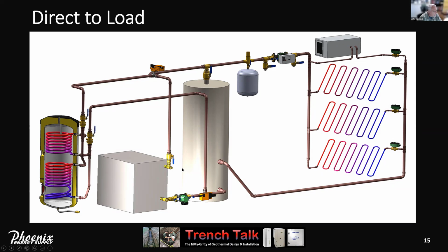There are some, quote, rules of thumb. I'd say a minimum buffer tank size could be as low as 0.6 gallons per 1,000 BTUs of heating capacity under low load. So you're going to want to look at the heat pump capacity, let's say at about 50 degree entering source water. That way, under low load, that's the kind of condition you might have. So a 5-ton is probably going to be close to 60,000 BTUs at 50 degree entering water. I would only go down to that 0.6 gallons per 1,000 BTUs if we have demand enabled, because if there's at least one zone calling, that too will act like a heat rejector and allow the buffer tank to behave as if it were a little bigger.